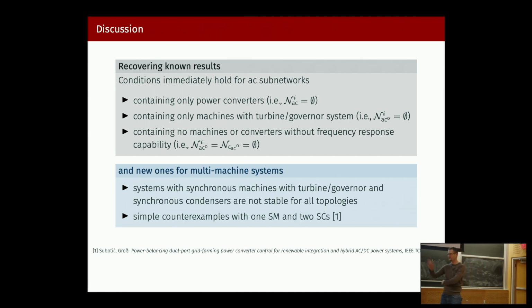And this is where your statement comes in - I mean, this is only true under very crude assumptions. Interestingly enough, it also recovers the case that if you have no machines or converters that do not respond to frequency, so if you have converters and machines and they all respond to frequency or DC voltage imbalances, you're also fine. And that, at least for that subset of control, was kind of known before.